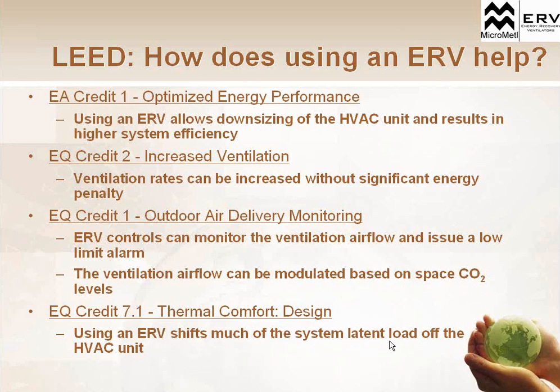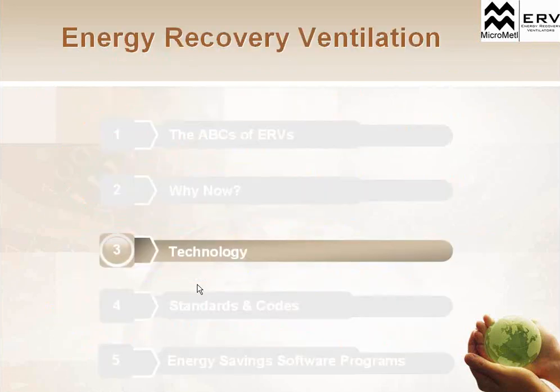One of the other credits is thermal comfort. Because we're handling that humidity, that latent load, we're taking a lot of that stress off the HVAC system, and we're getting better humidity control out of the system. We're either pre-dehumidifying or humidifying the space before that outside air comes in. So we're taking a lot of that load off the HVAC system and being able to get better control of the humidity in our space. So that's some of the LEED applications of an ERV.